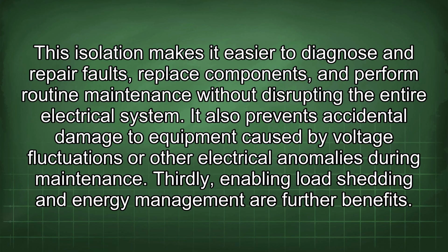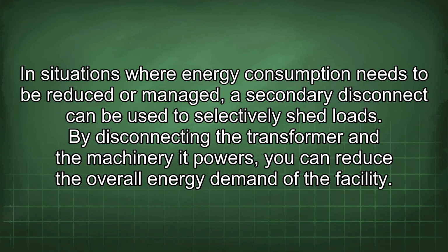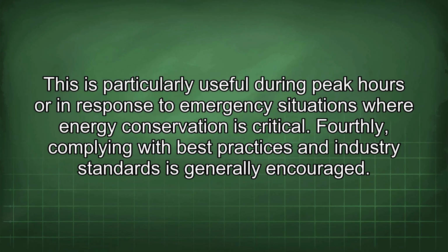Thirdly, enabling load shedding and energy management are further benefits. In situations where energy consumption needs to be reduced or managed, a secondary disconnect can be used to selectively shed loads. By disconnecting the transformer and the machinery it powers, you can reduce the overall energy demand of the facility. This is particularly useful during peak hours or in response to emergency situations where energy conservation is critical.